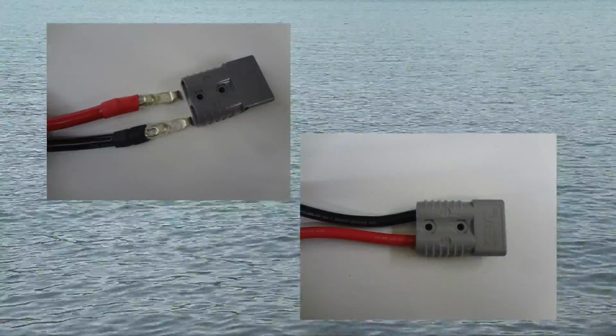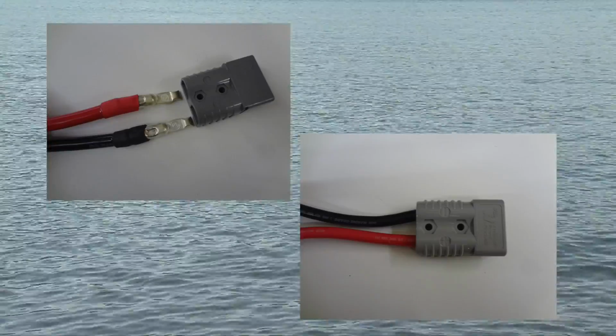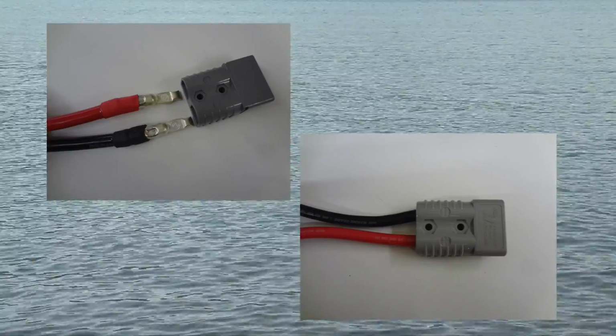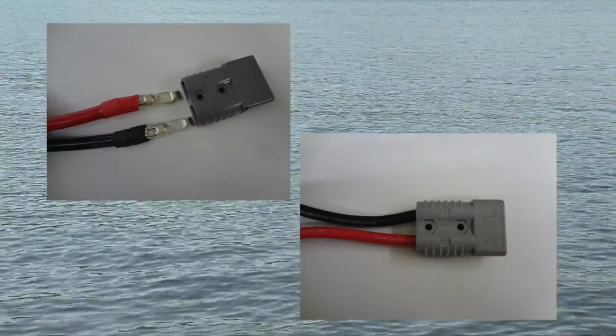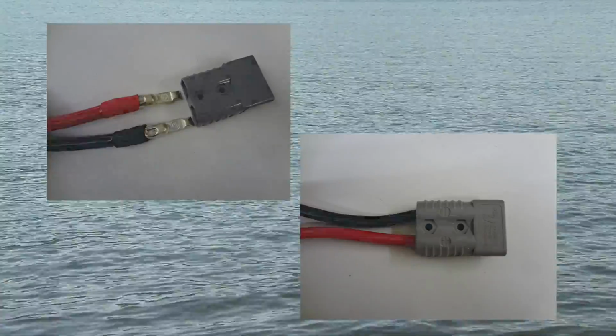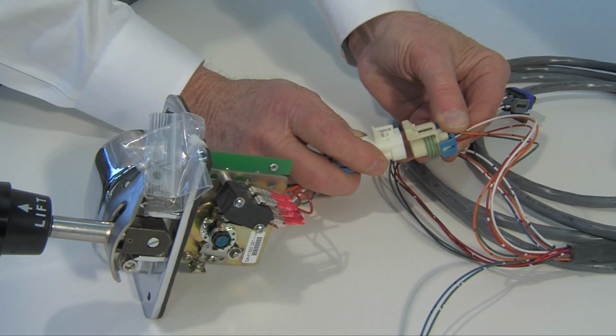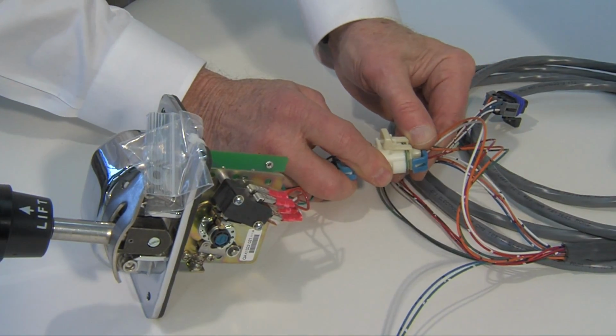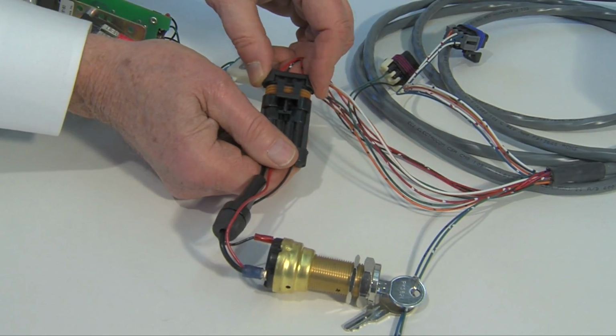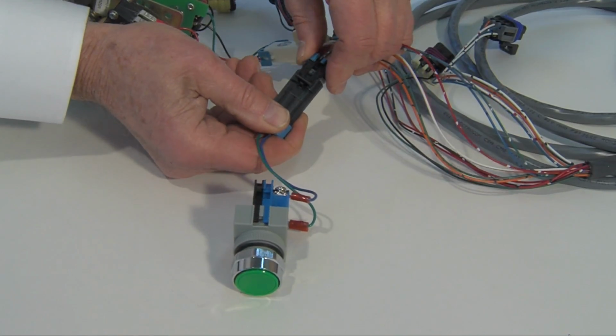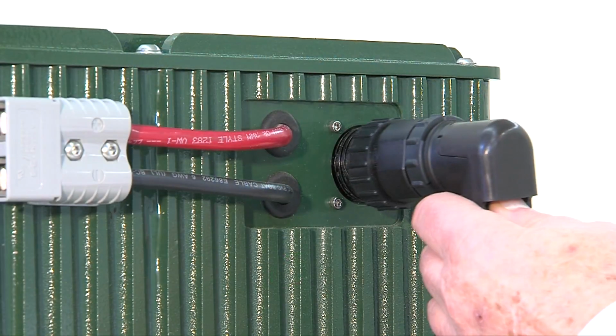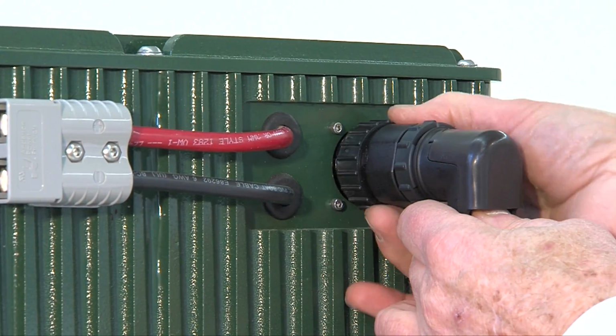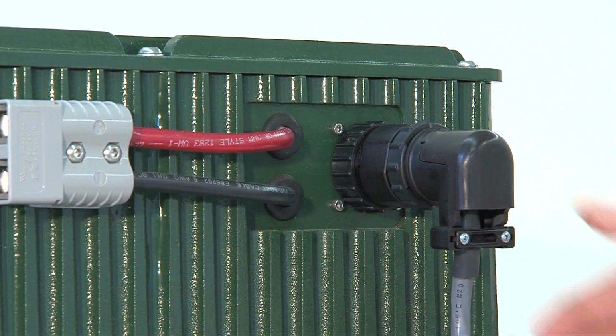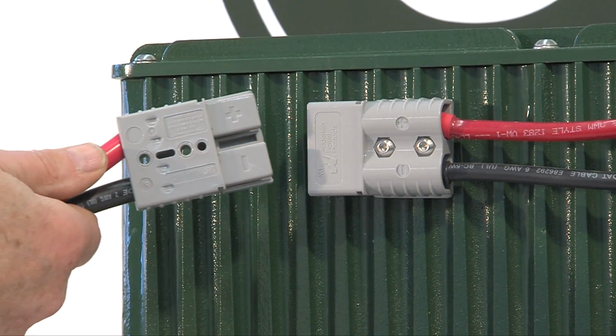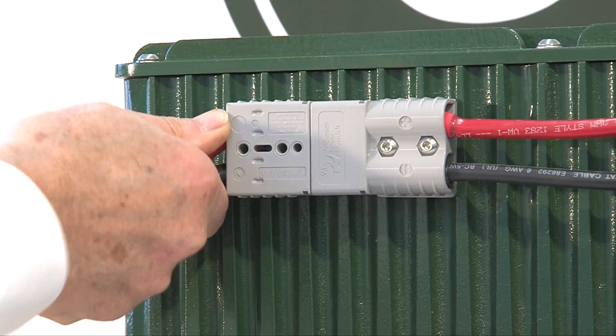After being properly fused and bonded, the positive and negative conductors from the battery bus bars will be terminated in an Anderson connector which plugs directly into the AL-KO motor on the side of the motor casting. With all connections in place, plug together the AL-KO pre-wired harnesses to test the system. All of the components have unique receptacles, so there's no chance of getting an incorrect plug into a receptacle. No cutting, soldering, or wiring tools are needed. It's all been pre-wired and tested at the factory. Plug batteries into the AL-KO motor and you should be operational.